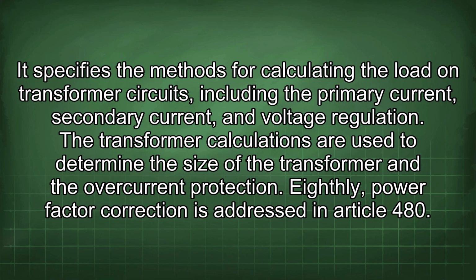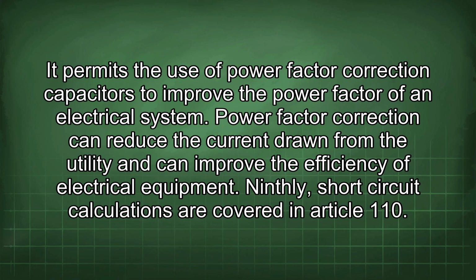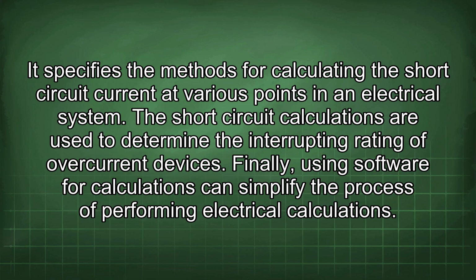Eighthly, power factor correction is addressed in Article 480. It permits the use of power factor correction capacitors to improve the power factor of an electrical system. Power factor correction can reduce the current drawn from the utility and can improve the efficiency of electrical equipment. Ninthly, short circuit calculations are covered in Article 110. It specifies the methods for calculating the short circuit current at various points in an electrical system. The short circuit calculations are used to determine the interrupting rating of overcurrent devices.